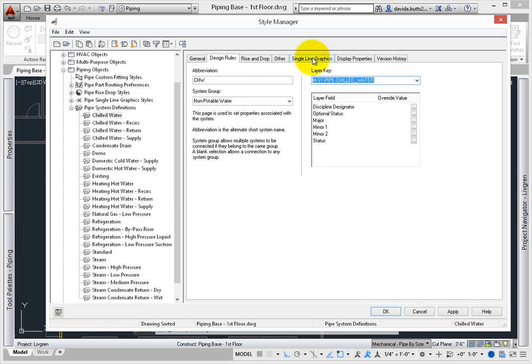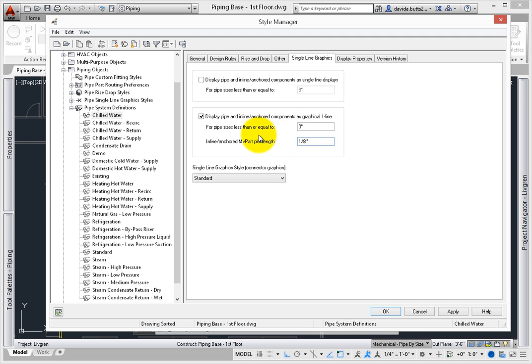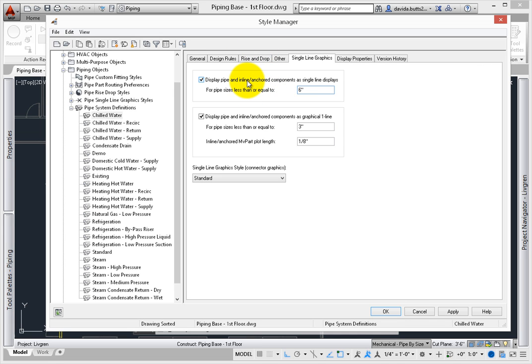Single line graphics are unique to pipe objects. For example, you might like to show all piping below 3 inches as a schematic single line, with all fitting tick marks the same size. On large scale drawings, with bigger pipe sizes, such as anything bigger than 3 inches, but less than 6 inches, the line shows as a single line, but also shows the tick marks of the actual size of the fittings.